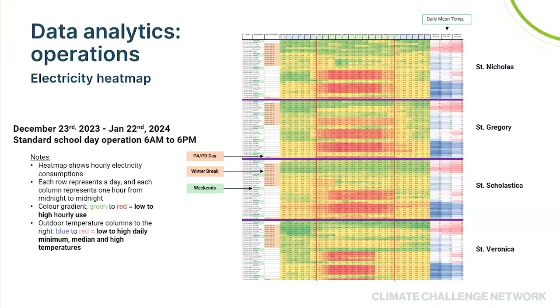The higher hourly electricity consumption relates to the darker colors, from green being very low to red being higher. And you can see pretty much the schedules are being tracked nice and closely. So this is electricity used to verify that operating hours on the school day are what they should be. But within here, you can see the school breaks as well. That's the orange colored rows that you see on the left-hand side. There's a PA day there, as it says, the winter break. You can see weekends. This is the best way, the only way that we know of practically across a large school board, of verifying that systems are running as intended. Next slide, please.